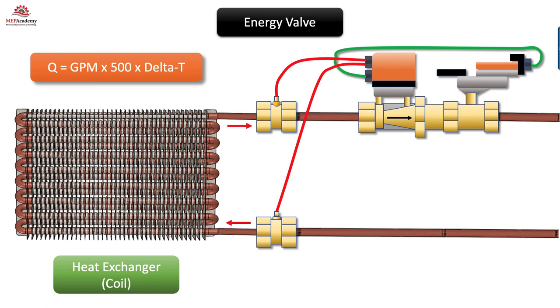To adjust the flow, or GPM, the energy valve will modulate the actuator on the control valve. The GPM is adjusted to reach the delta T set point of the energy valve.